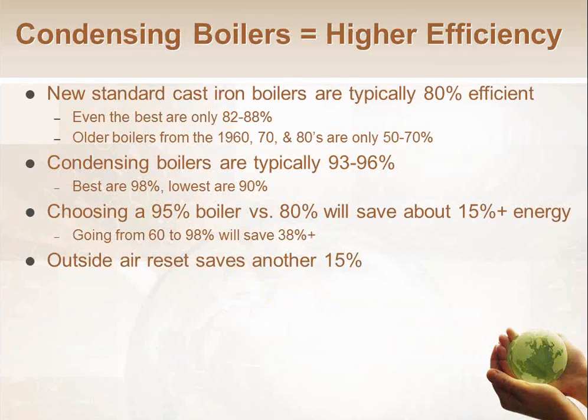So the reason to go to condensing boilers is to get higher efficiency. We get a lot of questions about, well, how efficient are things going to be? And how much money am I going to save? So the first thing to think about is, well, what do you have today, right? Your steel boiler or your copper boiler or your cast iron boiler, how efficient is it now? It's very common that I get an answer back, it's 80% efficient. And it very well may be, but depending on how old the boiler is and how well the boiler has been maintained, that 80% originally rated boiler 30 years ago may not be operating at 80% anymore.